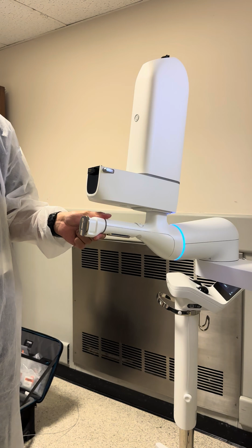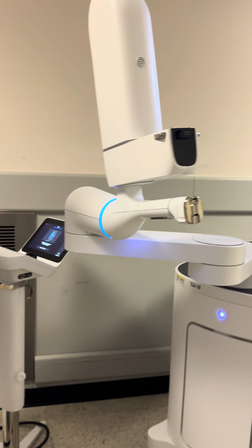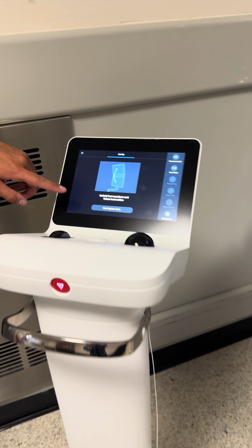it locks in place. What we want to do is we just want to create enough clearance, kind of like that Da Vinci when it does its system startup test, in order for that to happen. Once we move the arm on the screen, you'll see it says start system test, and I'll just press the button.